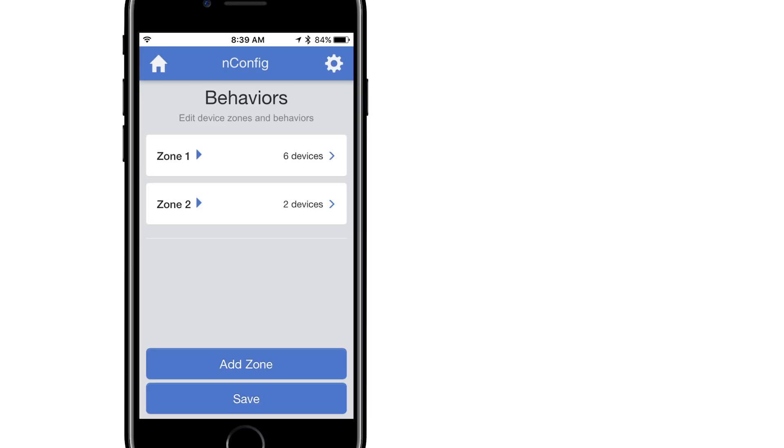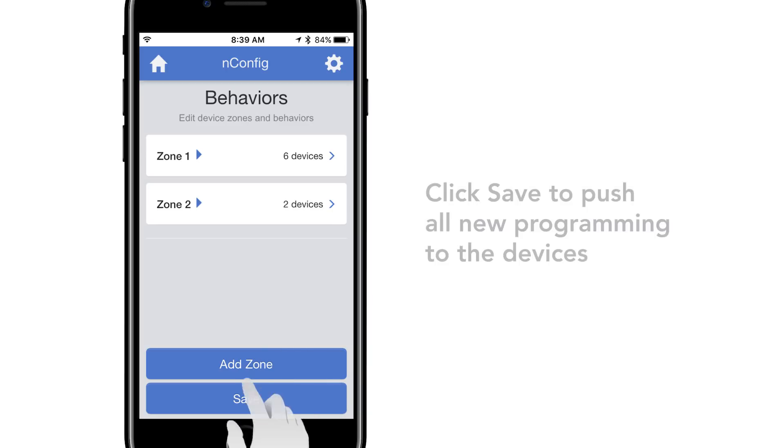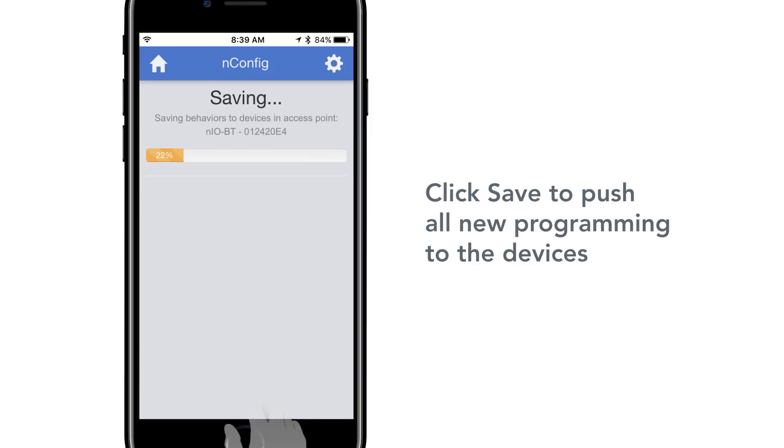When adding devices to zones, it is important to note that occupancy sensors and photocells can typically only exist in a single zone. Once all zones have been created and appropriate behavior selected, select Save to push all new programming to the devices.